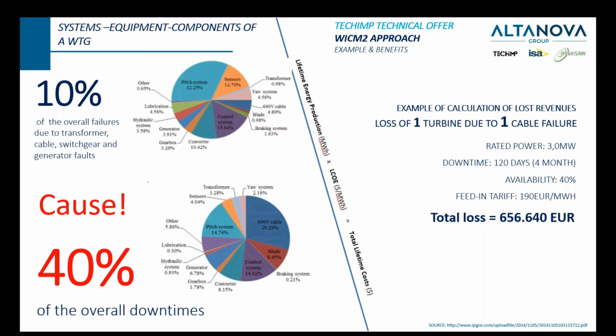There are different types of causes of failure. But the cost of the failure isn't equal to the downtime. So different causes of failure have different effects on the downtime. Here is a summary: about 10% of the overall failures are due to power apparatus failures, such as transformer, cable, switchgear, and generator faults. And this 10% of failures contributes to 40% of overall downtime. Apparently, such downtime has a big impact on the economy of wind farm operations. And that is the reason we need to do something to prevent or to reduce such failures.